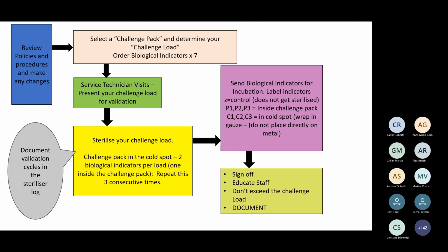When you're processing those biological indicators, please make sure that you don't put them right up against metal, against an instrument. Please wrap them in a piece of gauze or a bit of lint-free towel or something, because if they're sitting up straight against metal, then the metal can cause stress on the plastic, and then when they're processed, they can split, and then you'll have to do the whole biological indicators again. So always wrap them, protect them from metal.